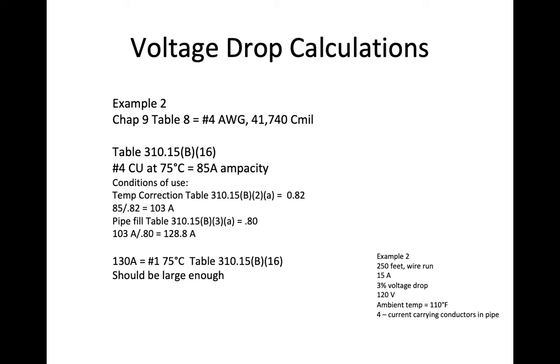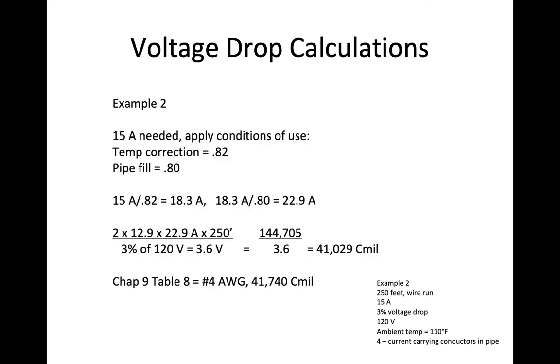So I go back to table 310-15B-16, run my finger down the 75 degree column, and I find that I need a number 1 conductor to get 15 amps, 250 feet away, through 110 degree ambient air temperature, and 4 current carrying conductors in a pipe. And that's how you do it.